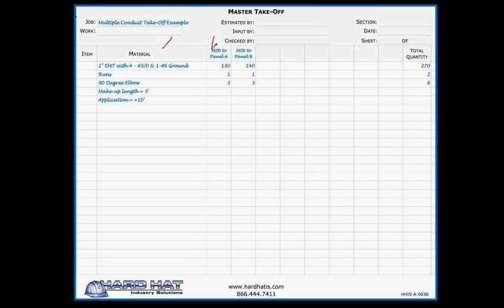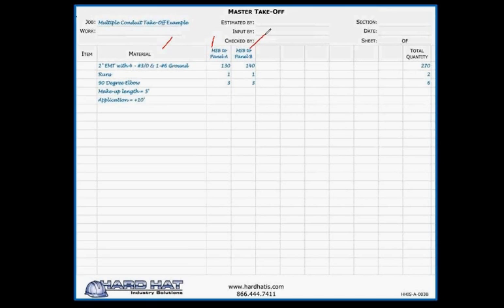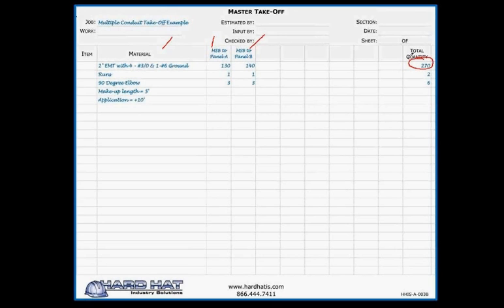To the right, I've labeled the column at the top, notating that each feeder runs from which panel to which panel, in this case from MSB to panel A or from MSB to panel B. Below the column MSB to panel A, I've written the length of conduit for that particular run, number of runs, quantity of elbows, and in this case, the conduit length that the scalex showed was 130 feet for panel A. Same goes for panel B. Okay, now at the far right, I totaled the amount of each one. You'll notice I showed the total amount or footage of conduit at 270 feet, the total number of elbows and the total number of runs.